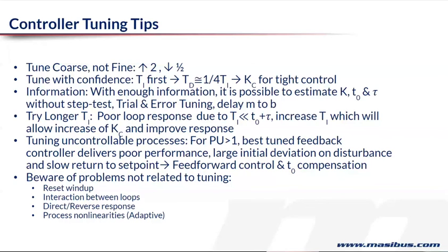Tune coarse, not fine. So if you are increasing the P band, or you are increasing the integral value, just go and double it. If you are decreasing any of the parameters, just halve it. Don't go 5%, 10% that way. Otherwise, it may take you a full day to tune the process. So this is the first thumb rule: tune coarse, not fine.